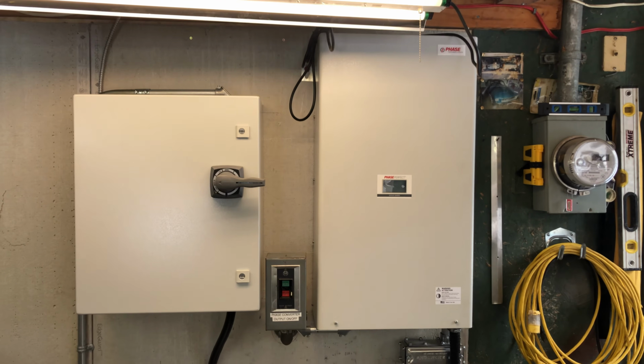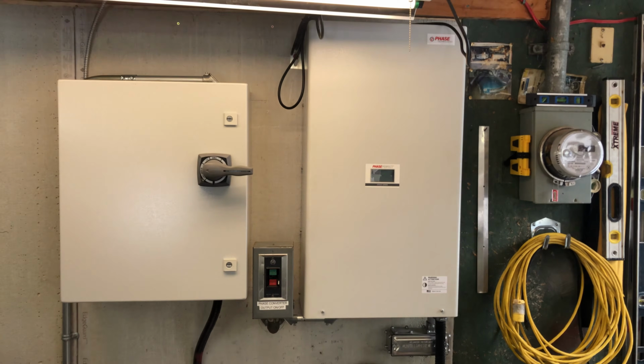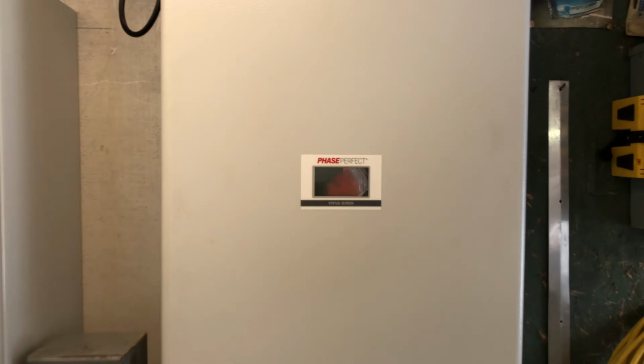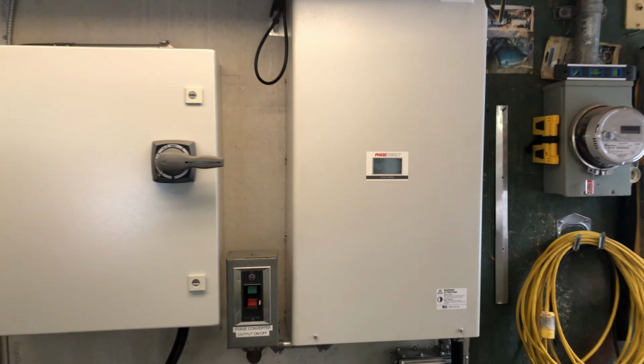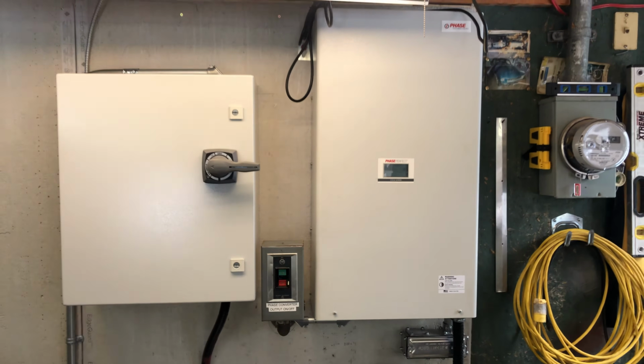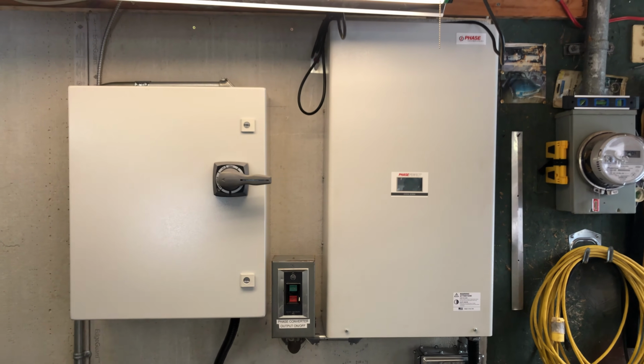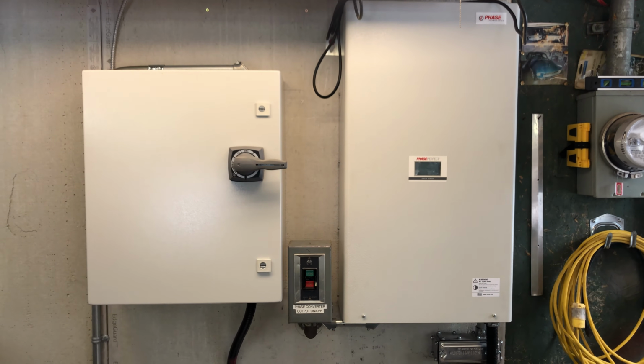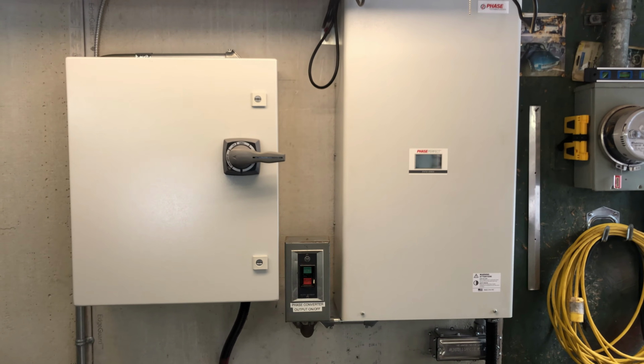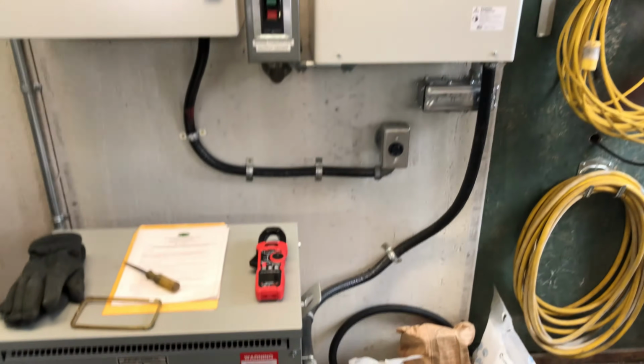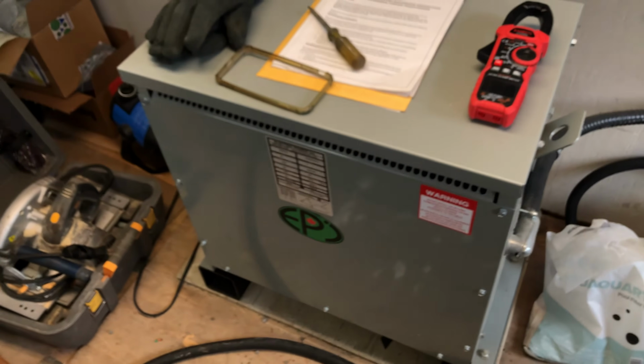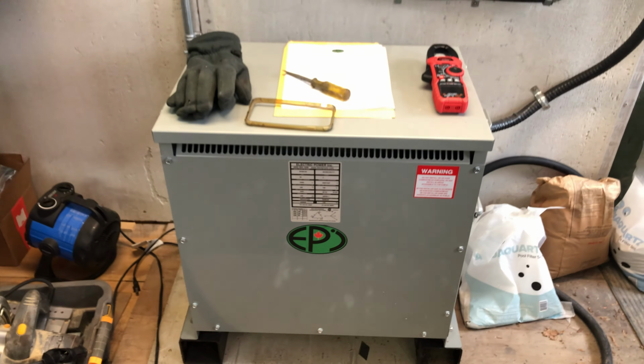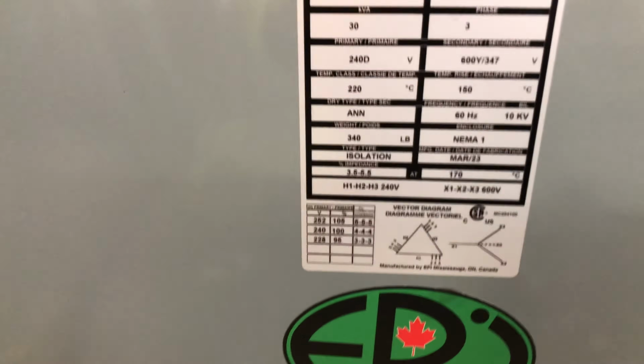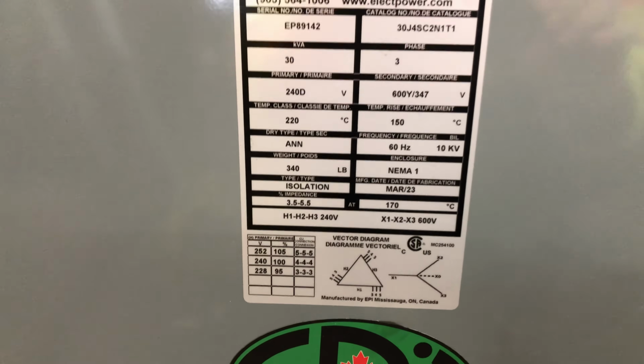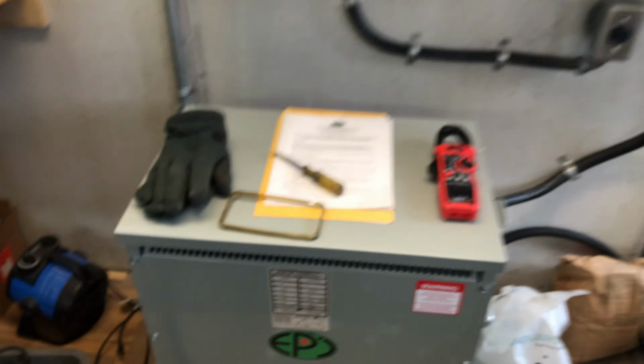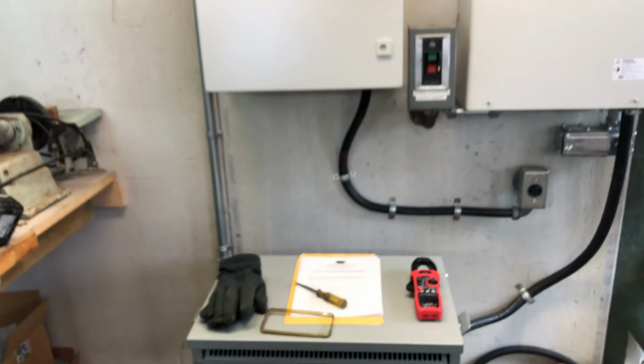So I'll just briefly go over the setup for the electrical for the industrial robot. Starting here is a 20 horsepower phase converter, and right now I have it running off a 100 amp breaker, but ideally it should be on a 125 amp breaker according to the manual, but so far I haven't run into any problems on a 100 amp breaker. So single phase comes into there, 3-phase comes out at 240 volts and goes into a 30 kVA transformer. And this is an isolating transformer, and you want an isolating transformer because otherwise you get a high leg out of the phase converter, and I'll go over that in depth in another video.